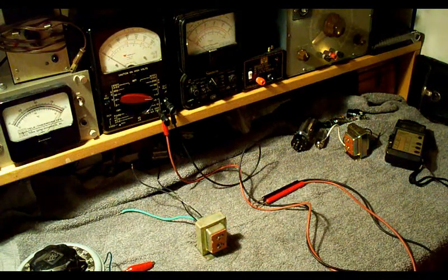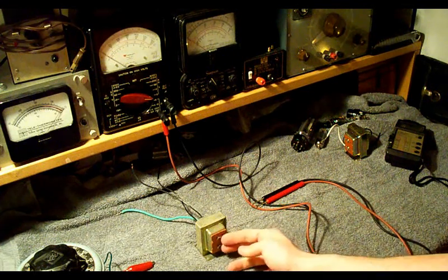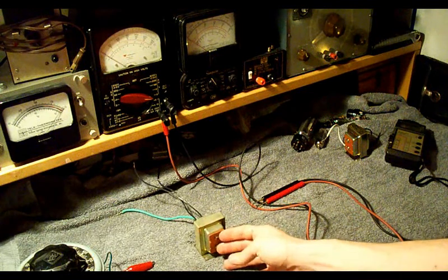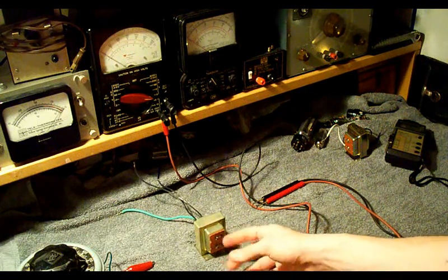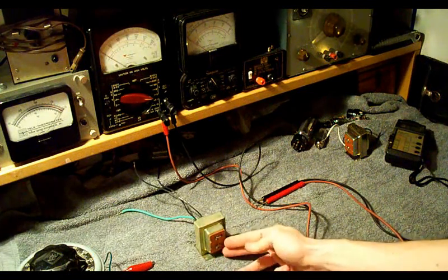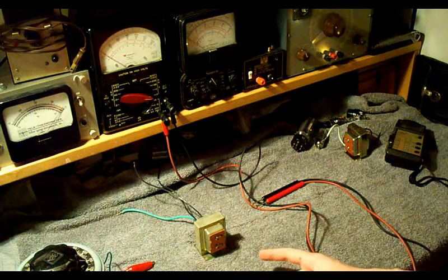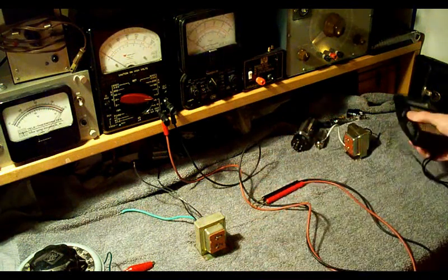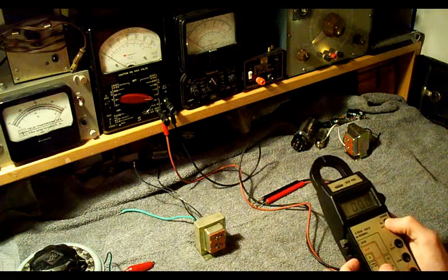Because if this transformer was installed in a circuit and your doorbell all of a sudden quit working, you went to see if your breaker was tripped, it wasn't tripped, so you would assume this transformer would be okay to touch. You go up here to start unscrewing these normally low voltage terminals, you're going to get one heck of a shock if you have 120 volts sitting across these terminals. That is not supposed to happen. And I can go ahead and verify that with my DMM here, one of my digital meters.